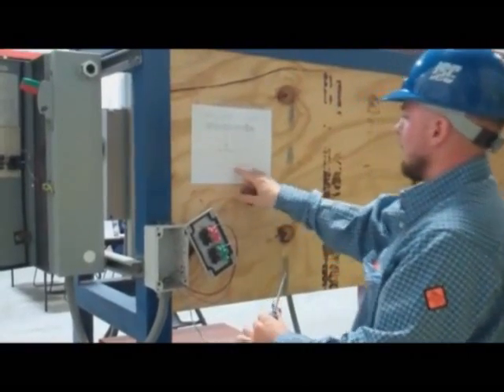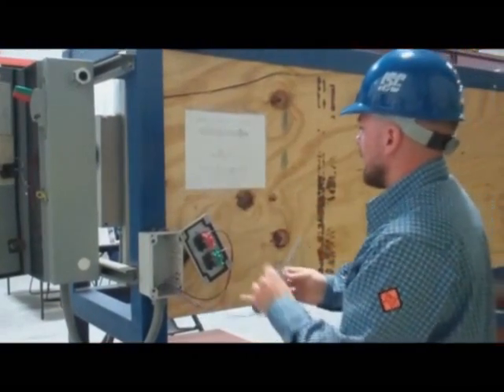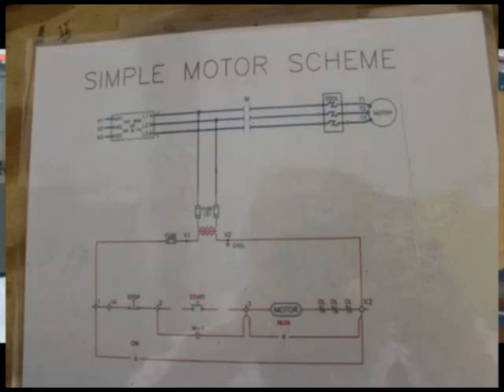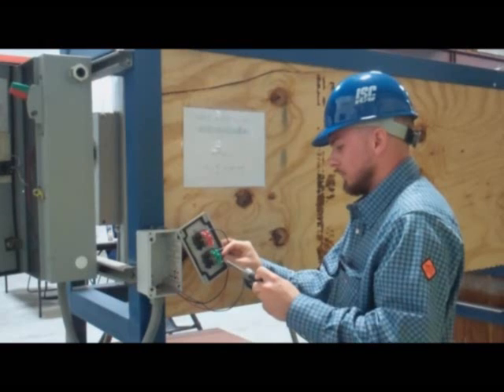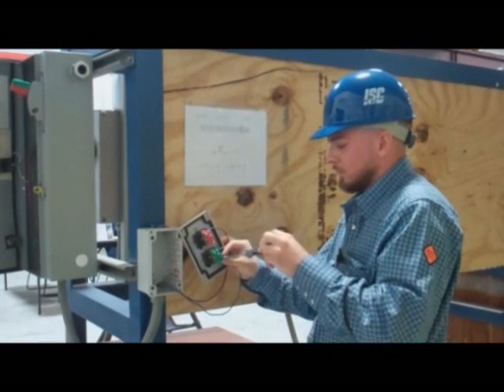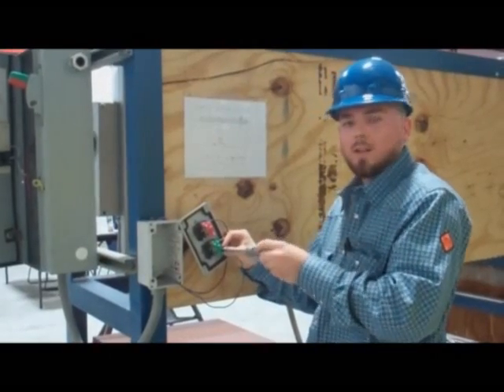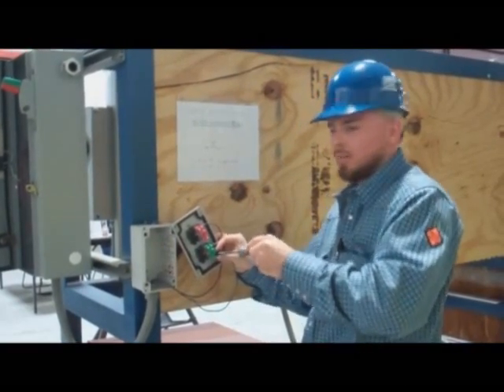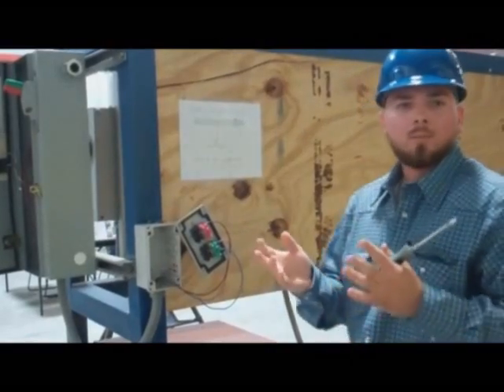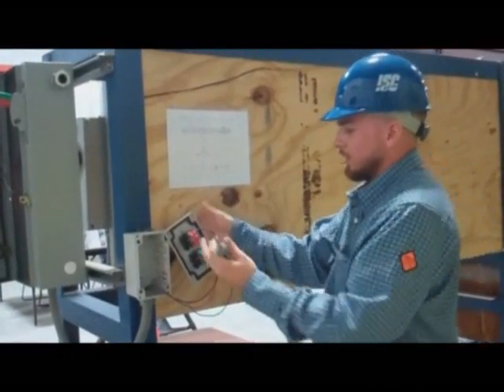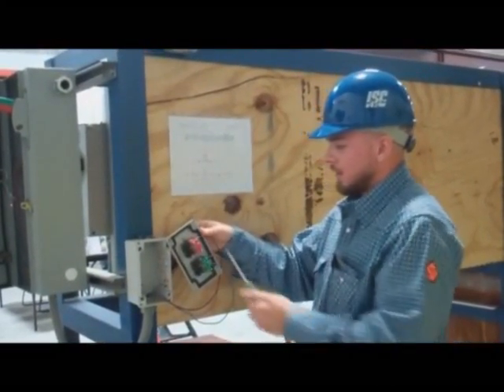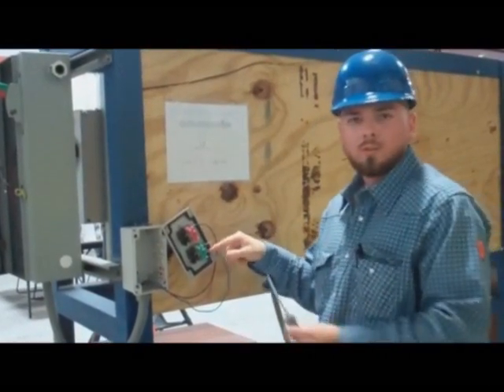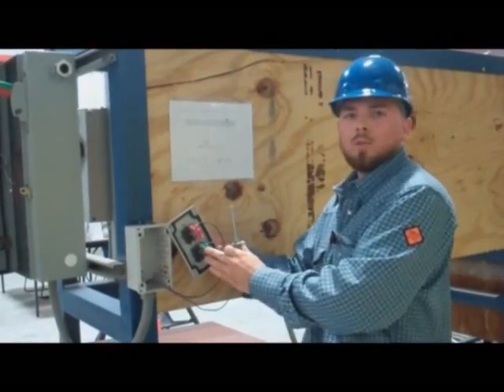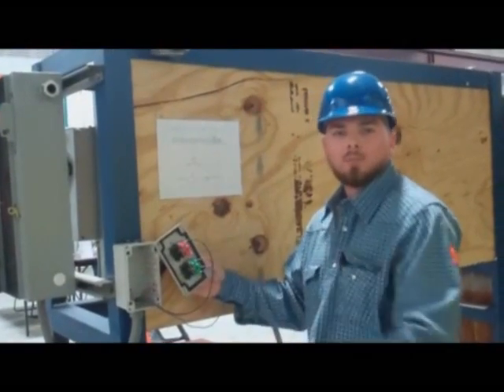You're going to find your 3 on your wiring diagram. It's going to be on the normally open on the start. And what normally open, normally closed means is normally open, your contacts are always open. And normally closed, it's simple, your contacts are always closed. So for example, on the stop button, it's always closed, so you're always going to be sending power to your start, because these are normally open. So when you push that down, it'll close the contacts, and that's what will get your motor to start.